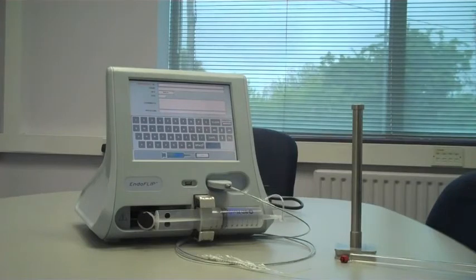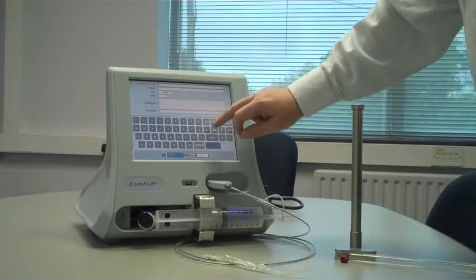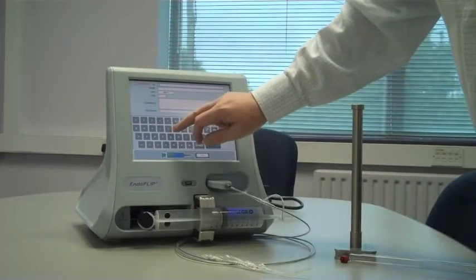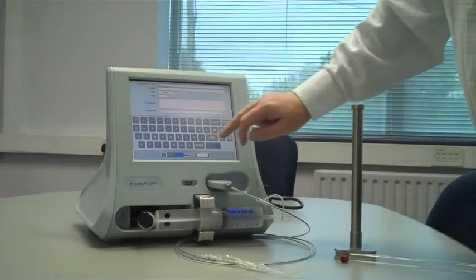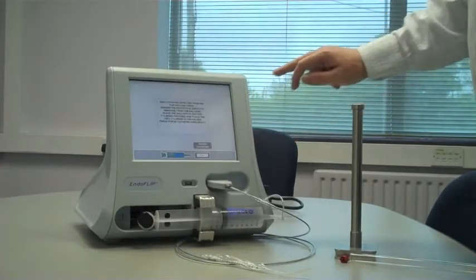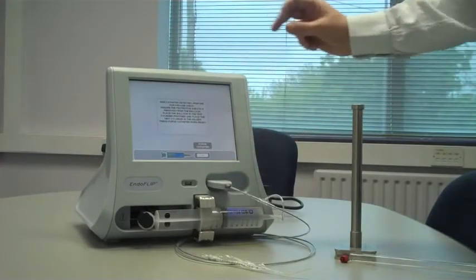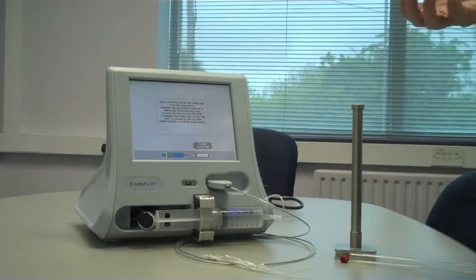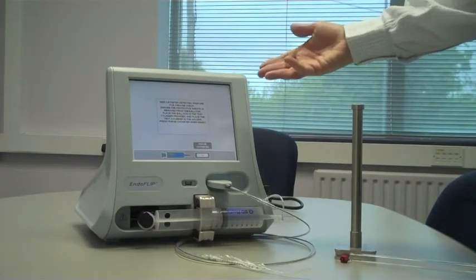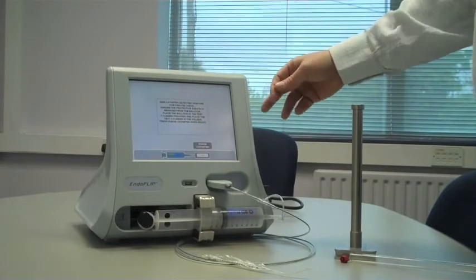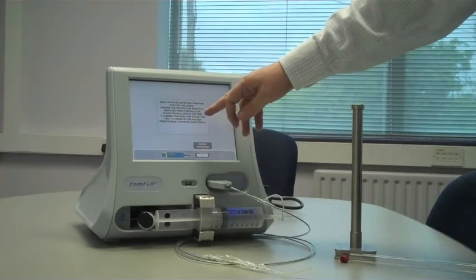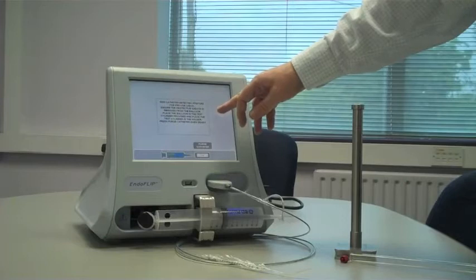We are then asked for the patient ID. So for instance, in this case, we'll type in patient 1, say PT1, and hit continue. You then get a message that says new catheter detected, prepare for pre-use check, ensure the protective sheath is removed, which we've just done, and then place the balloon in the test cylinder provided.